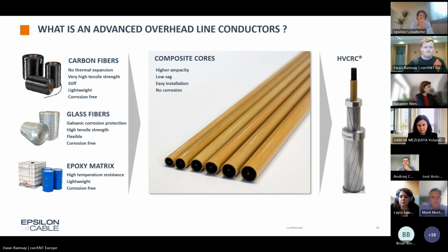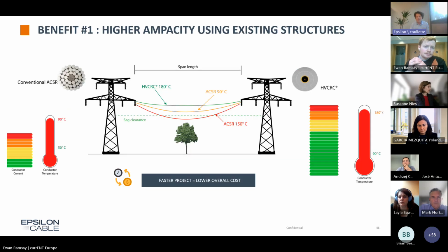Next slide please. The main benefit of this conductor is the ability to carry as much as twice the ampacity compared to a standard conductor, using the existing structures. How is it possible? Because the maximum operating temperature for these composite conductors is up to 180 degrees, double the limitation of a steel reinforced conductor, which we know sags at temperatures higher than 90 degrees.